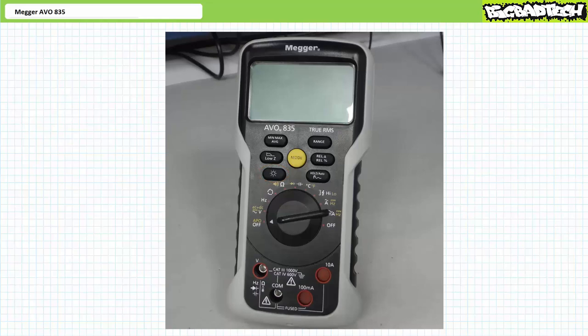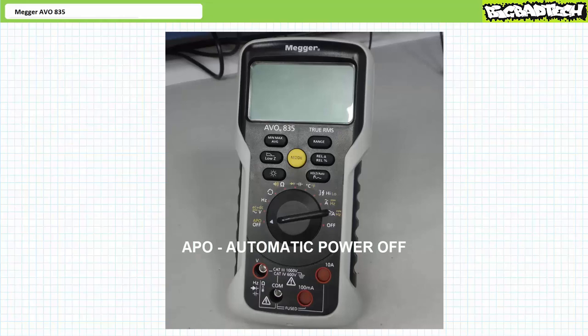Speaking of batteries, another handy feature on the Megger AVO 835 is APO, which stands for Automatic Power Off. After a period of inactivity, the Megger AVO 835 automatically powers down to save batteries. This feature is normally engaged at startup. As handy as this feature is, you might want to keep the display powered up if you need to monitor properties over an extended period of time. To disable the Automatic Power Off option at startup, press and hold the yellow Center Mode button while you turn it on. Whatever function you switch to won't be interrupted by the Automatic Power Off, and the meter remains functional until you make the conscious decision to turn it off.